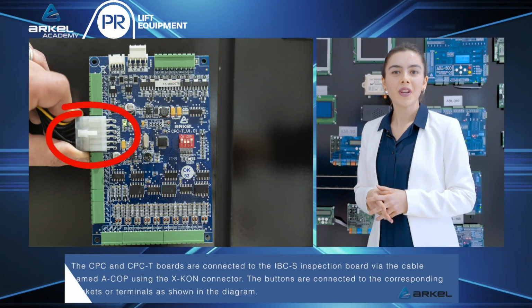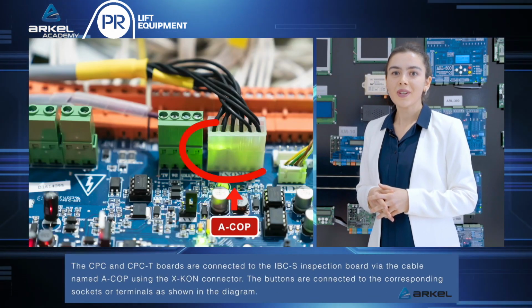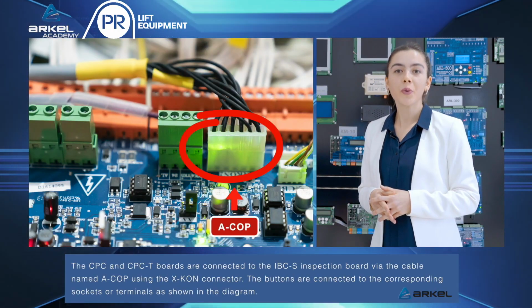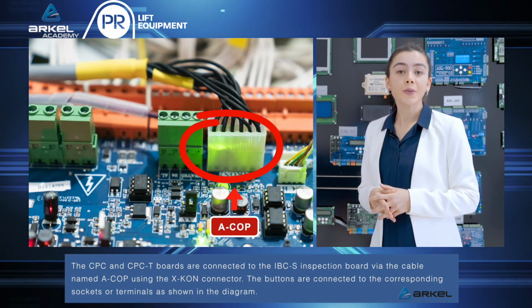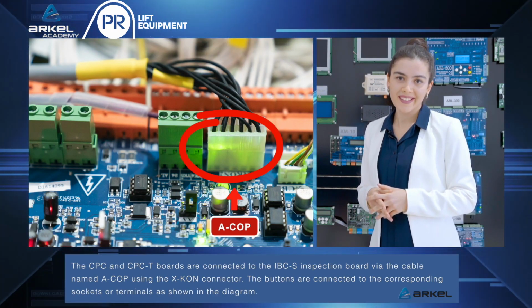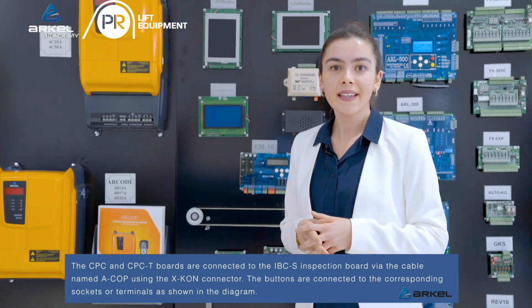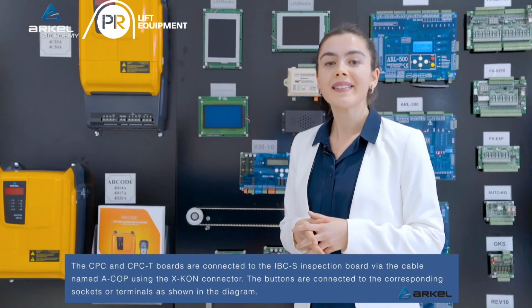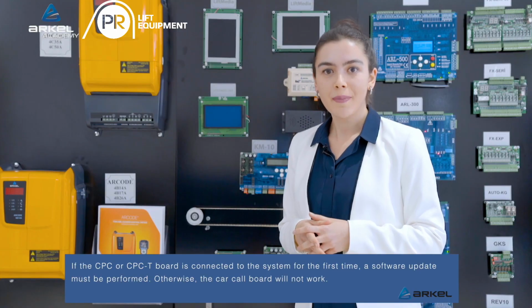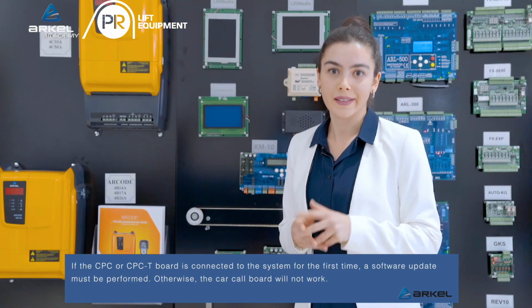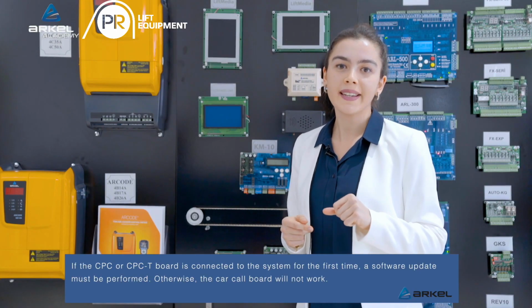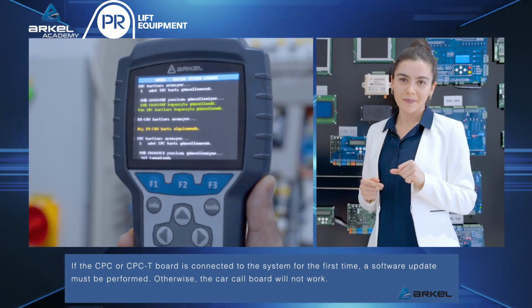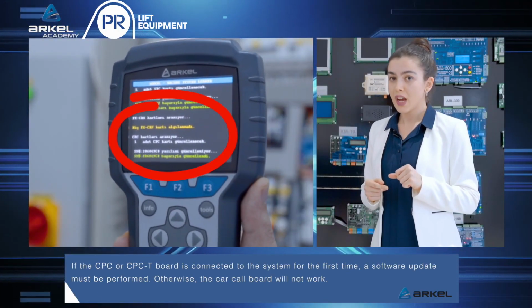The CPC and CPC-T boards are connected to the IBCS inspection board via the cable named ACOP using the X-KON connector. These buttons are connected to the corresponding sockets or terminals as shown in the diagram. If the CPC or CPC-T board is connected to the system for the first time, a software update must be performed. Otherwise, the car call board will not work.